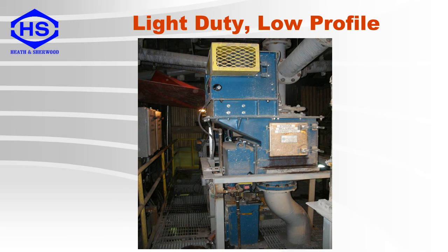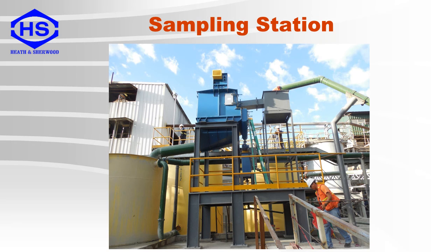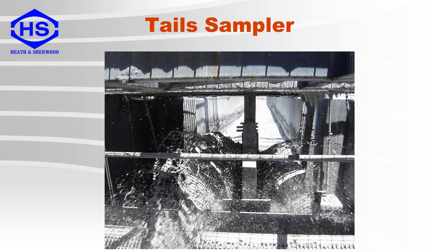This is a low-profile cross-stream sampler for use in locations where installation room is a problem — the distance between the inlet and outlet connections is minimized. Here is another example of a sampling station. The process line is connected to a collector tank, which is used to dissipate the pressure. This then feeds the primary sampler, which feeds a secondary sampler. Lastly, here is a tail stream sampler. You can see the cutter moving across the process flow. Because this flow is very large, there is also a lot of splashing occurring after the cutter.